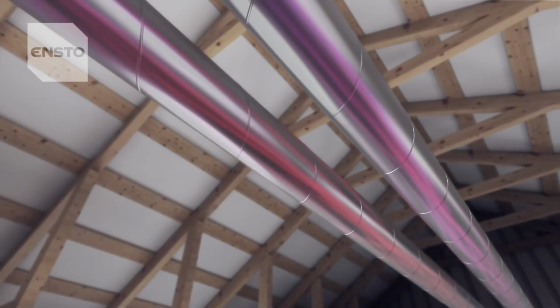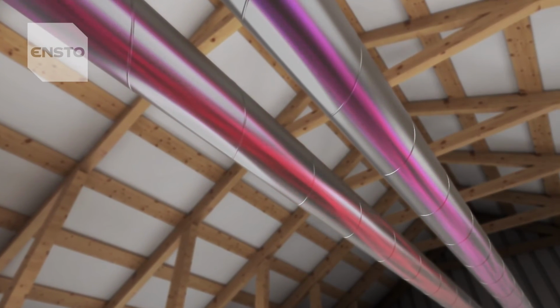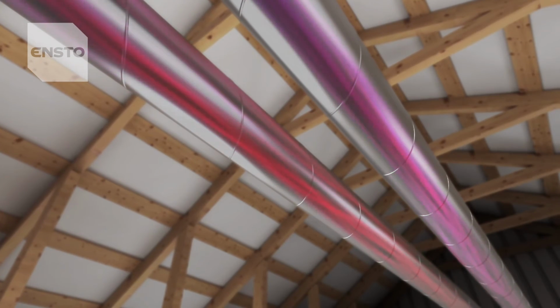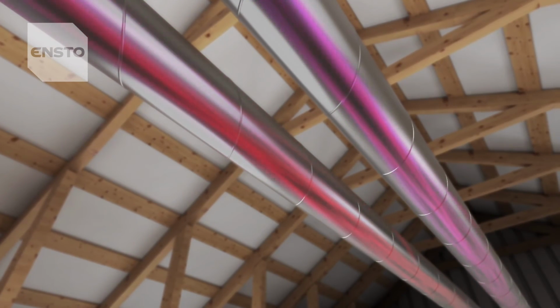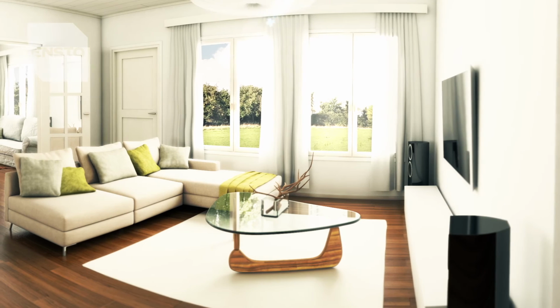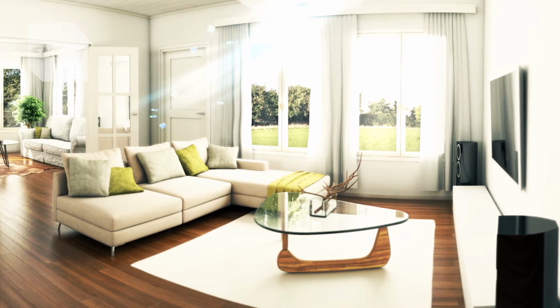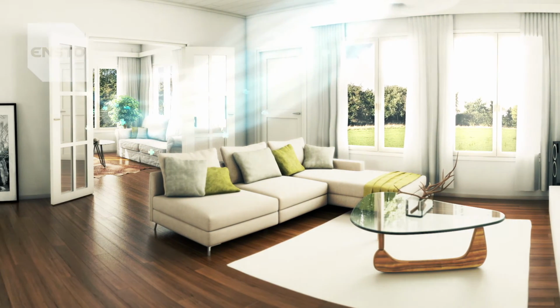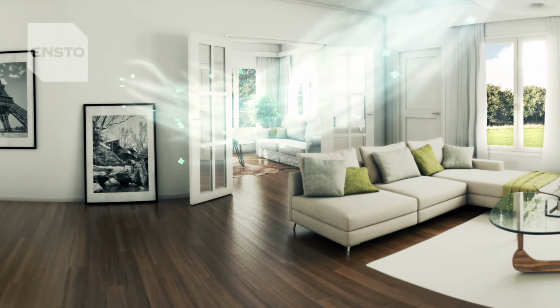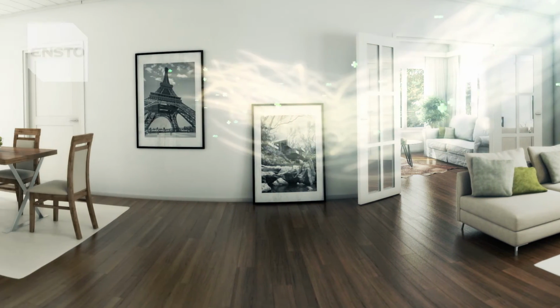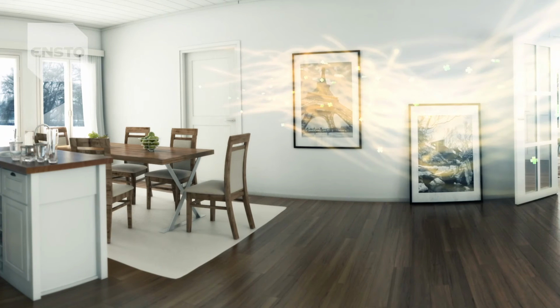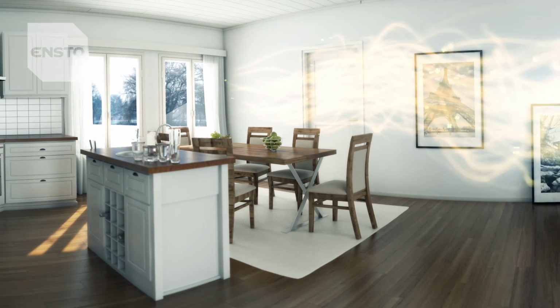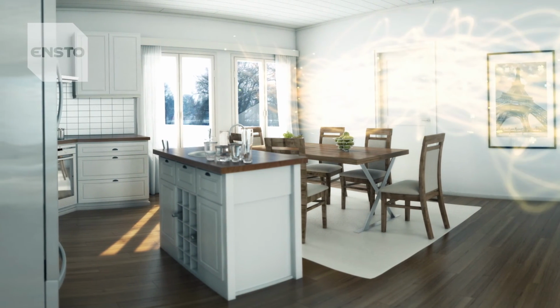The temperature efficiency of the rotating heat exchanger is extremely high, which means that most of the extract air's heat can be recovered. The rotating heat exchanger can also be used for heat recovery when the outdoor air temperature is higher than the extract air temperature. During winter, when the relative humidity of indoor air is often low, the rotating heat exchanger returns some of the extract air's humidity back to the supply air.